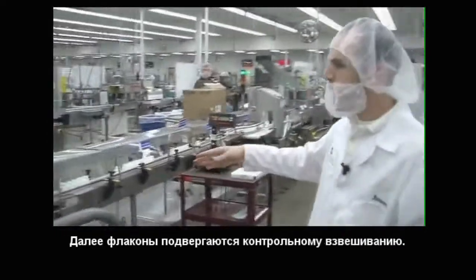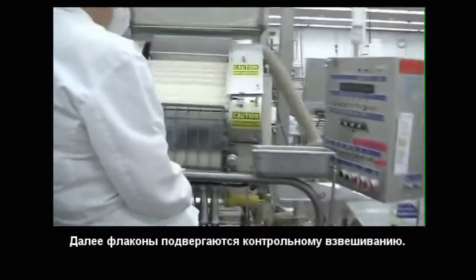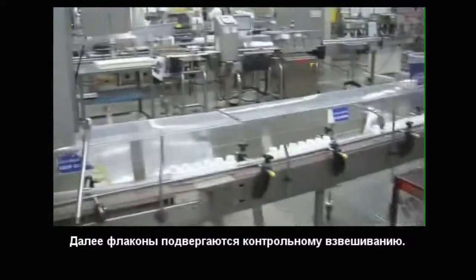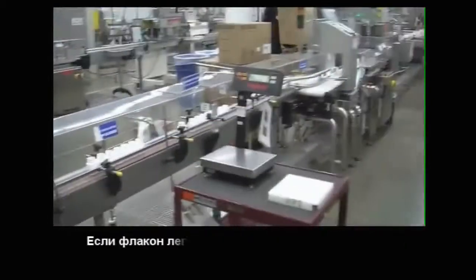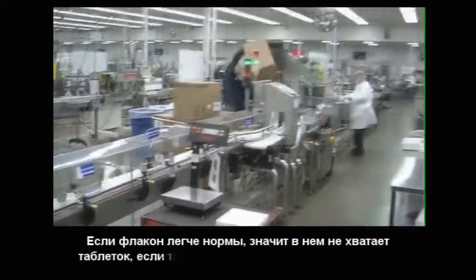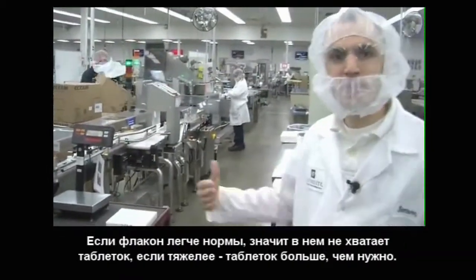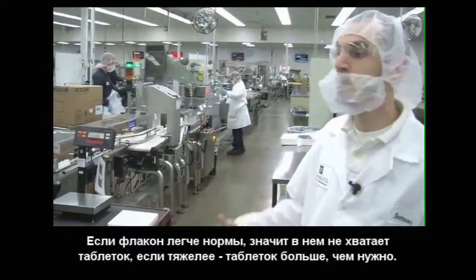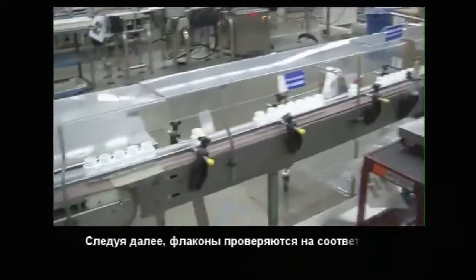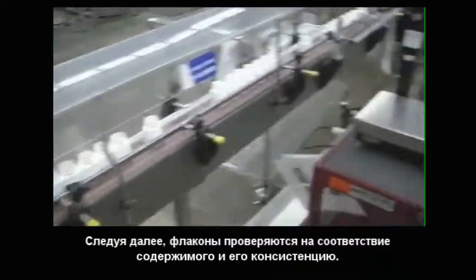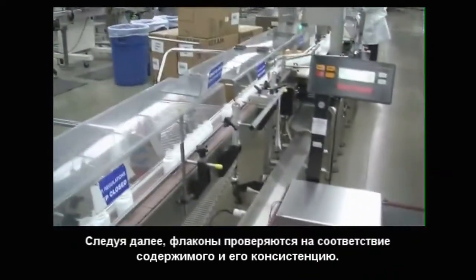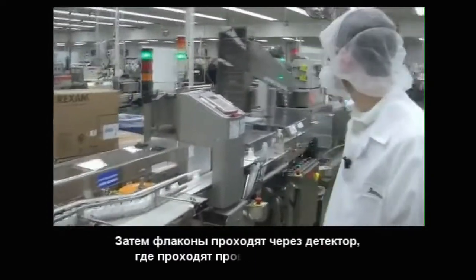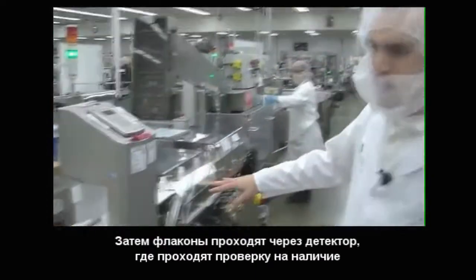After you go through that, the conveyor belt is going to go through a check weigher. This check weigher is going to see if a bottle is too light or too heavy. Too light means that they don't have enough tablets. Too heavy means that they have too many tablets. The conveyor belt will just shoot those bottles off the line so that there is consistency with all the tablet numbers. Going further through the line, we go through the metal detector.